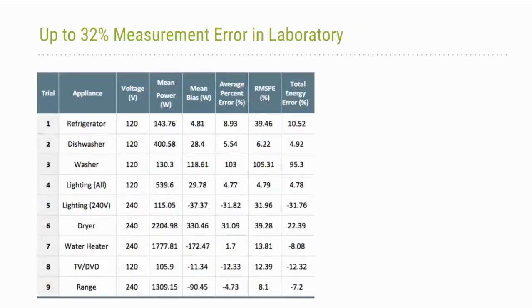This table shows the error measurements. If you focus on the right side, you'll see the total energy error. These sensors tend to perform a lot better for consistent loads that don't cycle much, for example the 120-volt lighting, as well as refrigeration and dishwasher, which tend to be more constant loads.